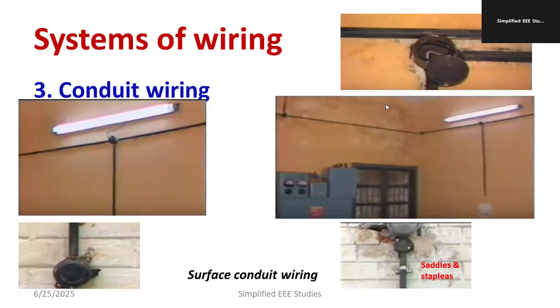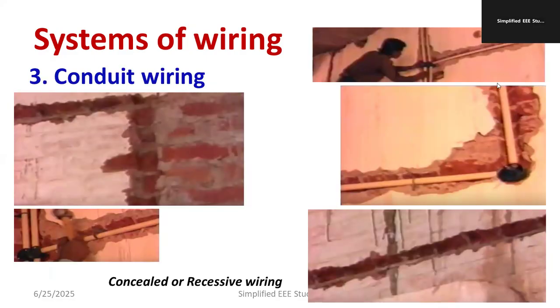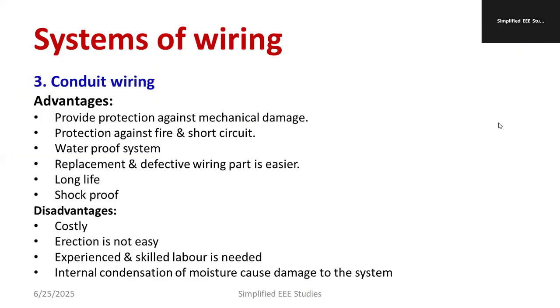The advantages of conduit wiring are protection against mechanical damage, fire, and short circuits; it is a waterproof system; defective parts can be replaced; it provides long life and is shock-proof. The setbacks are that it is expensive, erection is difficult, and once installed, any fault repair is very costly and disrupts the structure. Experienced and skilled labor is required to locate faults. Internal condensation of moisture can also cause damage to the system.